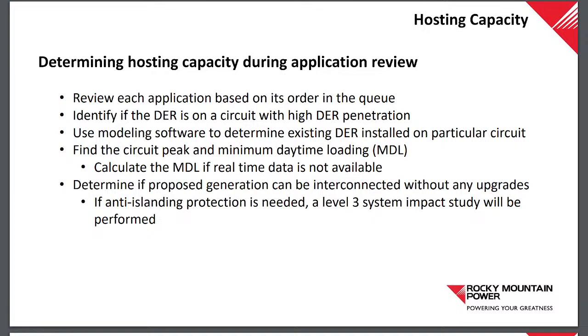Most of these circuits here in Utah, aside from a few rural ones, have SCADA, which is our real-time data, so what we see is an actual number. So at 11 a.m. on a Tuesday, we see the lowest time, and at that time and place, if we see, let's call it a megawatt, we know there was a megawatt of load with all the active generation generated. So that's an actual minimum load.